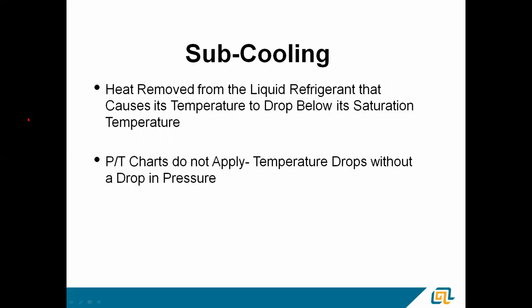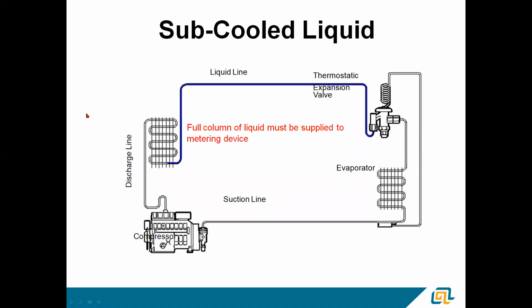Subcooling is heat removed from liquid refrigerant, causes its temperature to drop below its saturation temperature. So we look at our liquid gauge, maybe you see like 380 pounds. The liquid line would have its lower temperature. That's our subcooling. Pressure temperature charts do not apply. The temperature drops without a drop in pressure. Subcooled liquid exists in a very, very small spot of this system. The outlet of the condenser to the inlet of the TXV. It's the only place you'll find subcooled liquid.